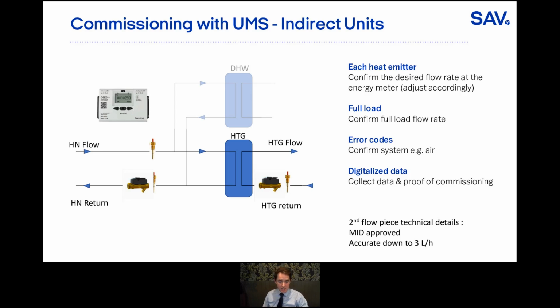You can do a full load test, making sure that the HIU is performing and the settings are put in properly for that full load. One of the big benefits as well is that it's all on the energy meter. So with the energy meter, you have your error codes. If you've got air in the system, which is a very big issue on the secondary sides, that can be highlighted. But also if you have issues with circulation, through to blockages or the pump, you can also see that with that energy meter.